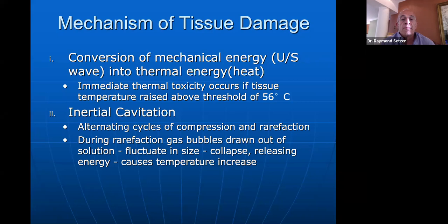The second way HIFU works is a thing called inertial cavitation. As the ultrasound wave passes through the tissue, we get alternating cycles of compression and rarefaction, or decompression. It's during these rarefaction phases that gas bubbles are drawn out of solution. These bubbles fluctuate in size, getting bigger and smaller, eventually getting bigger and bigger until they collapse, releasing energy. This adds to the temperature increase inside the fibroid.